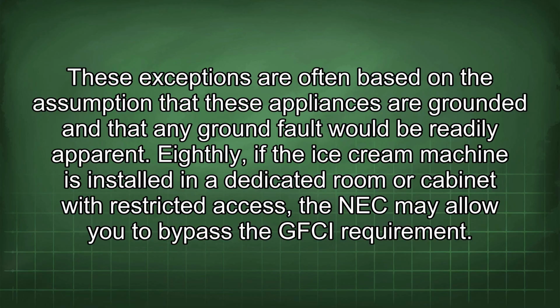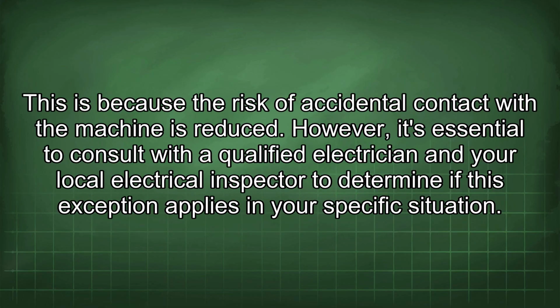Eighthly, if the ice cream machine is installed in a dedicated room or cabinet with restricted access, the NEC may allow you to bypass the GFCI requirement. This is because the risk of accidental contact with the machine is reduced. However, it's essential to consult with a qualified electrician and your local electrical inspector to determine if this exception applies in your specific situation.